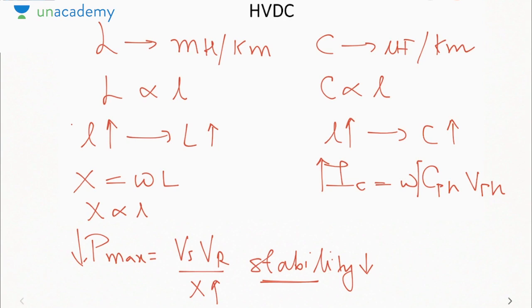In DC, there is no concept of frequency and reactance, so there is no stability problem. As well, frequency is 0, so there is no problem of the line charging current. Also, in AC, one of the main requirements of power transfer is that the frequency at both the ends must be the same. But in DC, there is no problem of frequency, that is, asynchronous power transfer is possible. That is, when both the ends have different frequencies, you can transfer the power by means of DC but not by AC. Suppose in case of the British system, the frequency is 50 Hz, whereas in the US the frequency is 60 Hz. So if you want to lay down a conductor to transfer power between the US and the UK, you need to use an HVDC link and not an AC link.